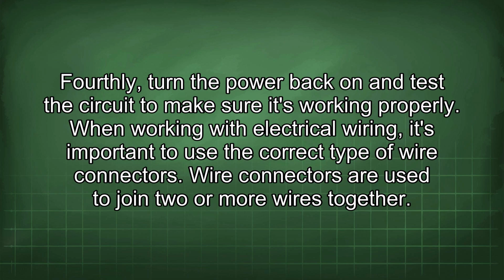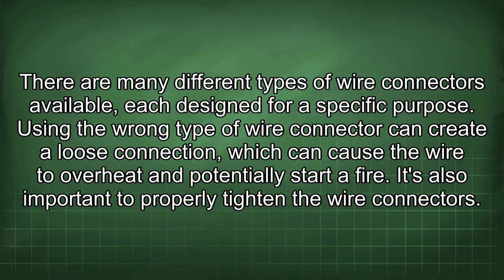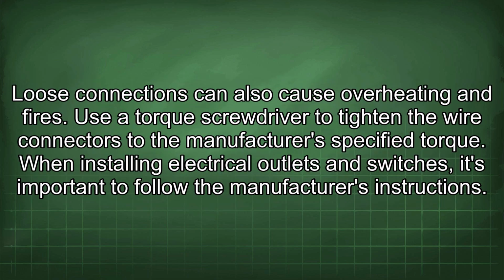When working with electrical wiring, it's important to use the correct type of wire connectors. Wire connectors are used to join two or more wires together. There are many different types of wire connectors available, each designed for a specific purpose. Using the wrong type of wire connector can create a loose connection, which can cause the wire to overheat and potentially start a fire. It's also important to properly tighten the wire connectors. Loose connections can also cause overheating and fires. Use a torque screwdriver to tighten the wire connectors to the manufacturer's specified torque.